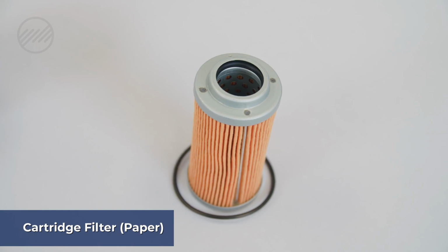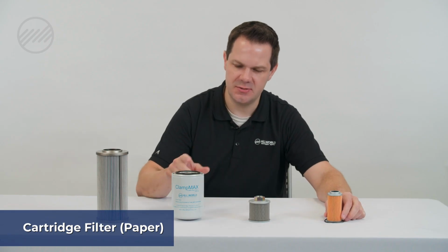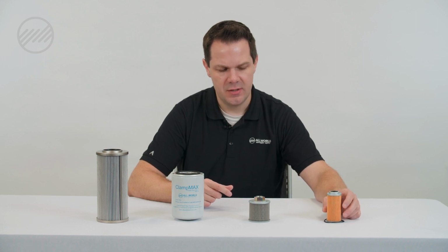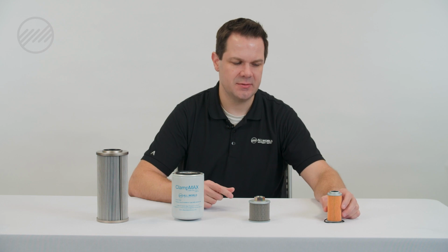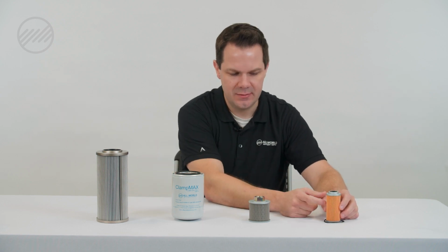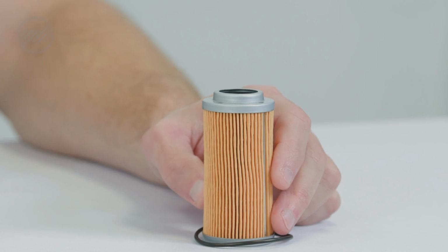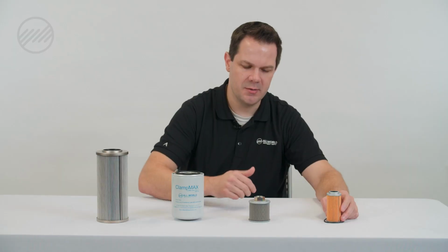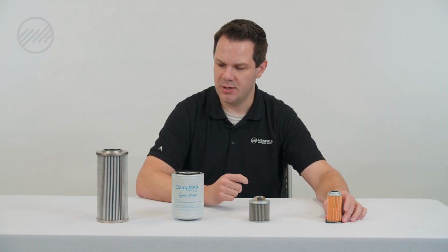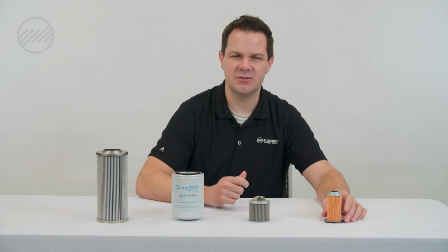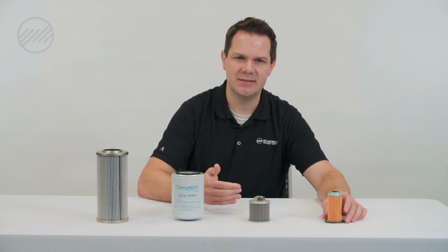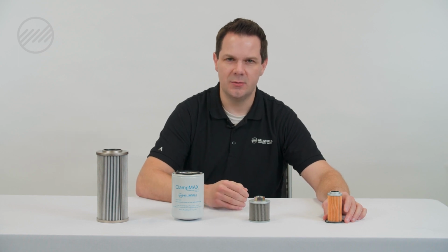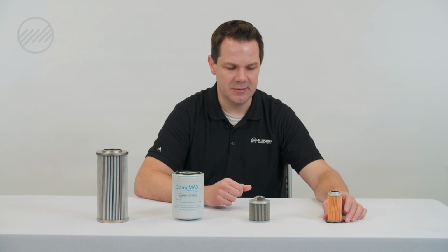The last filter I have here has similar characteristics to a couple of the others, where this can be found on a low pressure system. The differences, as you can possibly see, are the types of filtration or the media that's used. You can see cellulose or paper. You'll also see wire mesh, or stainless steel wire mesh. Those materials and medias vary based on the type of fluid you are filtering typically. Some have longer lifespans or are more durable for certain fluid types.